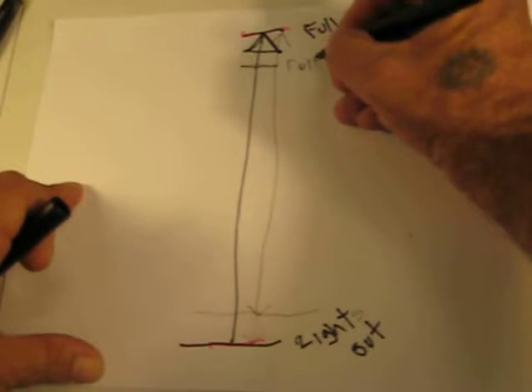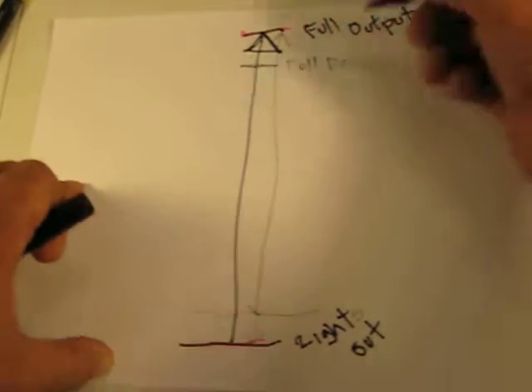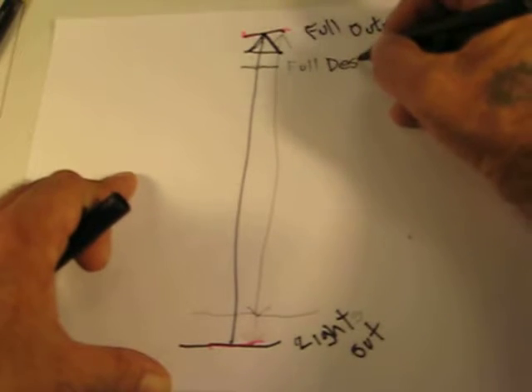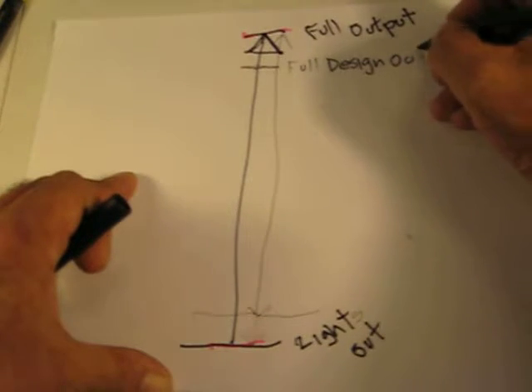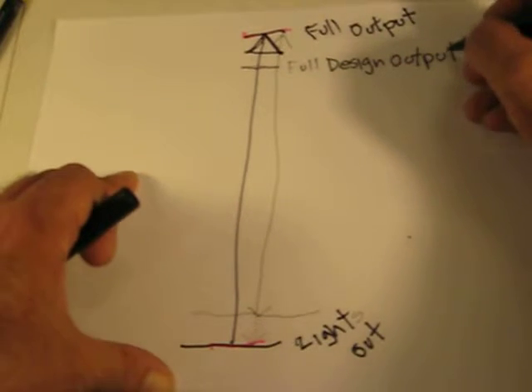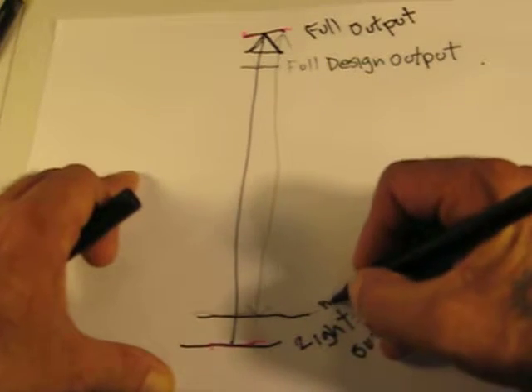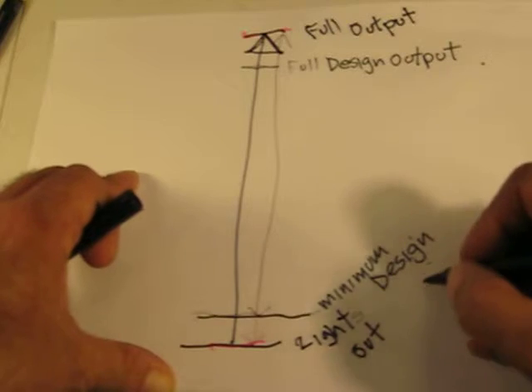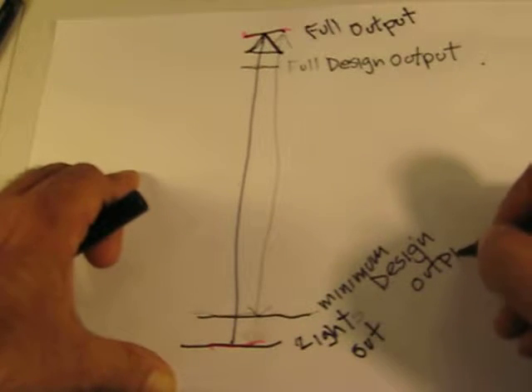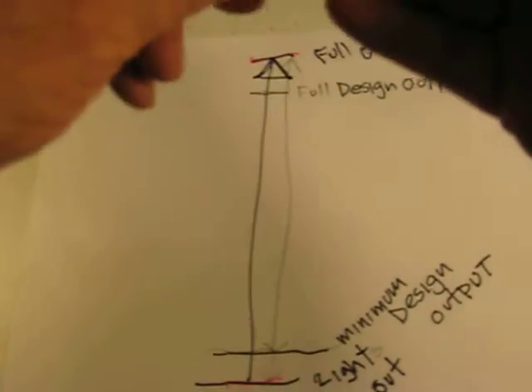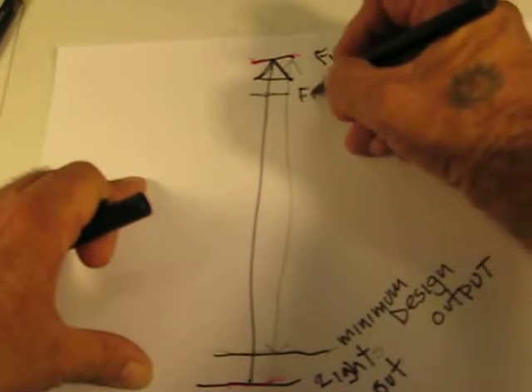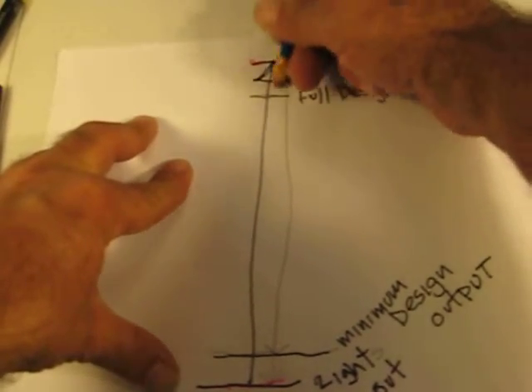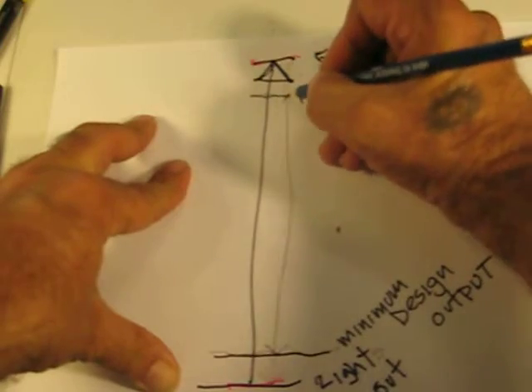This is typical of lighting installers — they will shave a little off the top when they put the thing together. So now we will not be able to manually dim between minimum design output and full output. We will actually have a dimming range between minimum design output and full design output. I've talked to people who put these systems in and they say they like to shave about five to six percent off the top to save the customers some money.